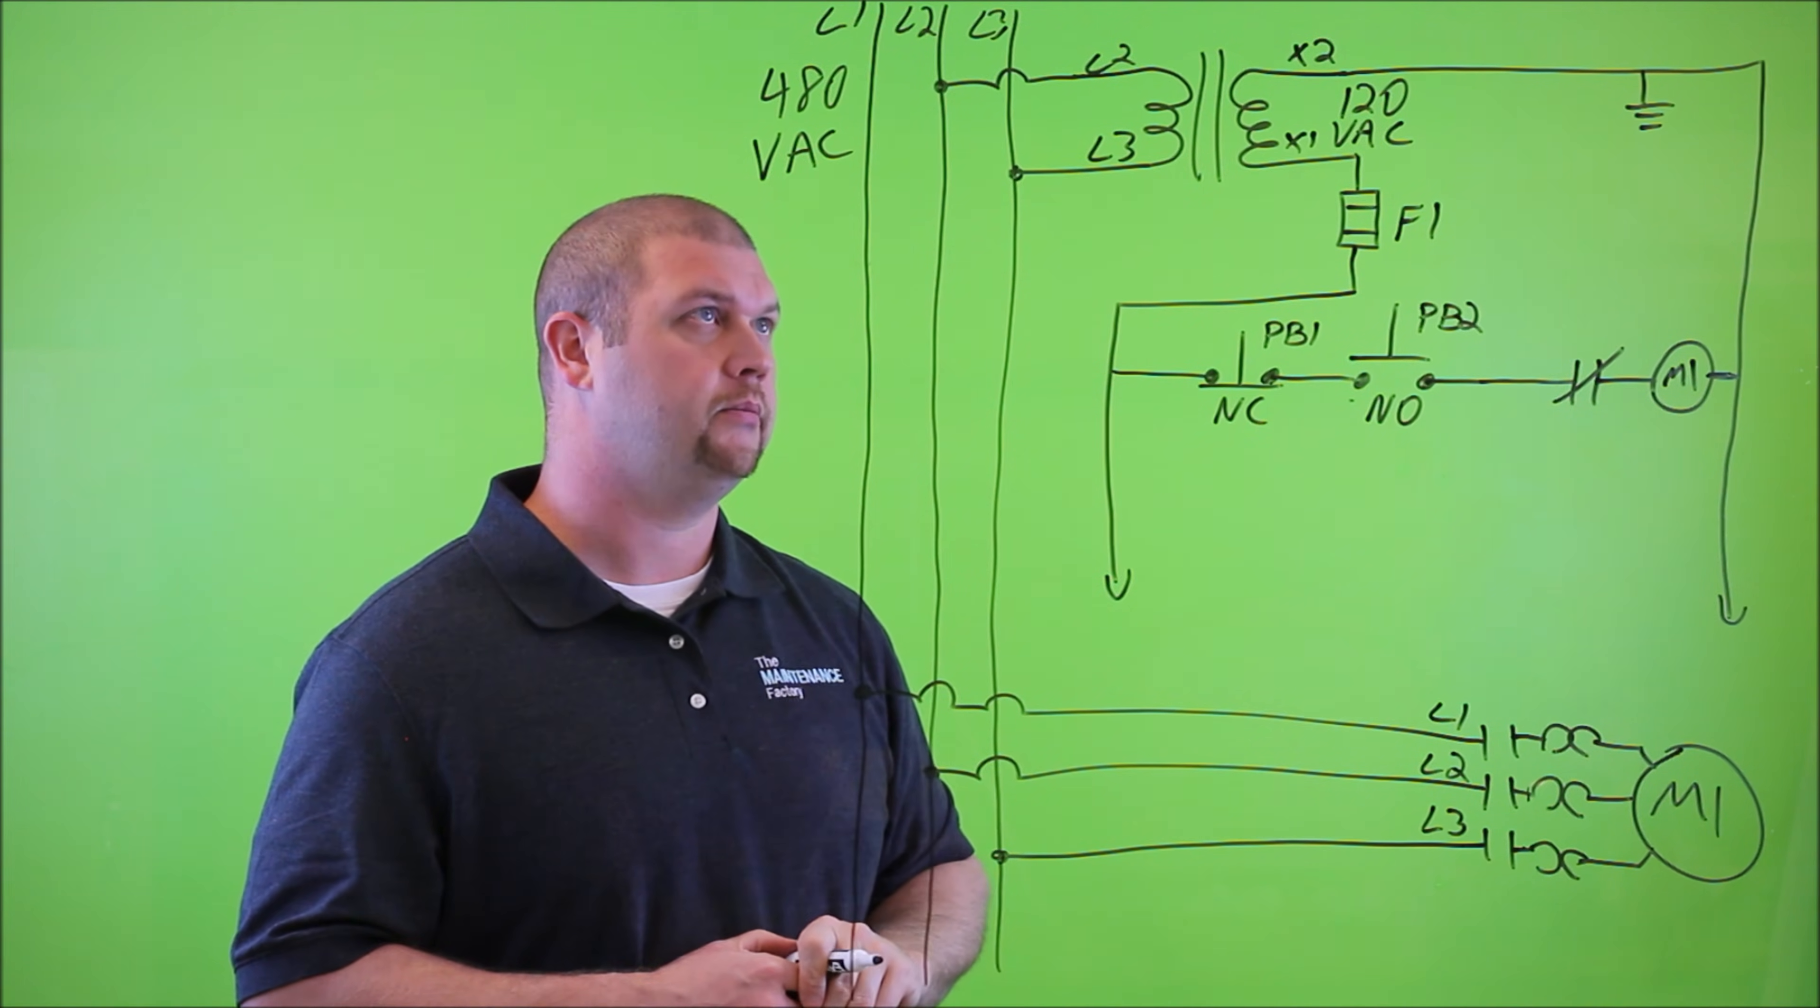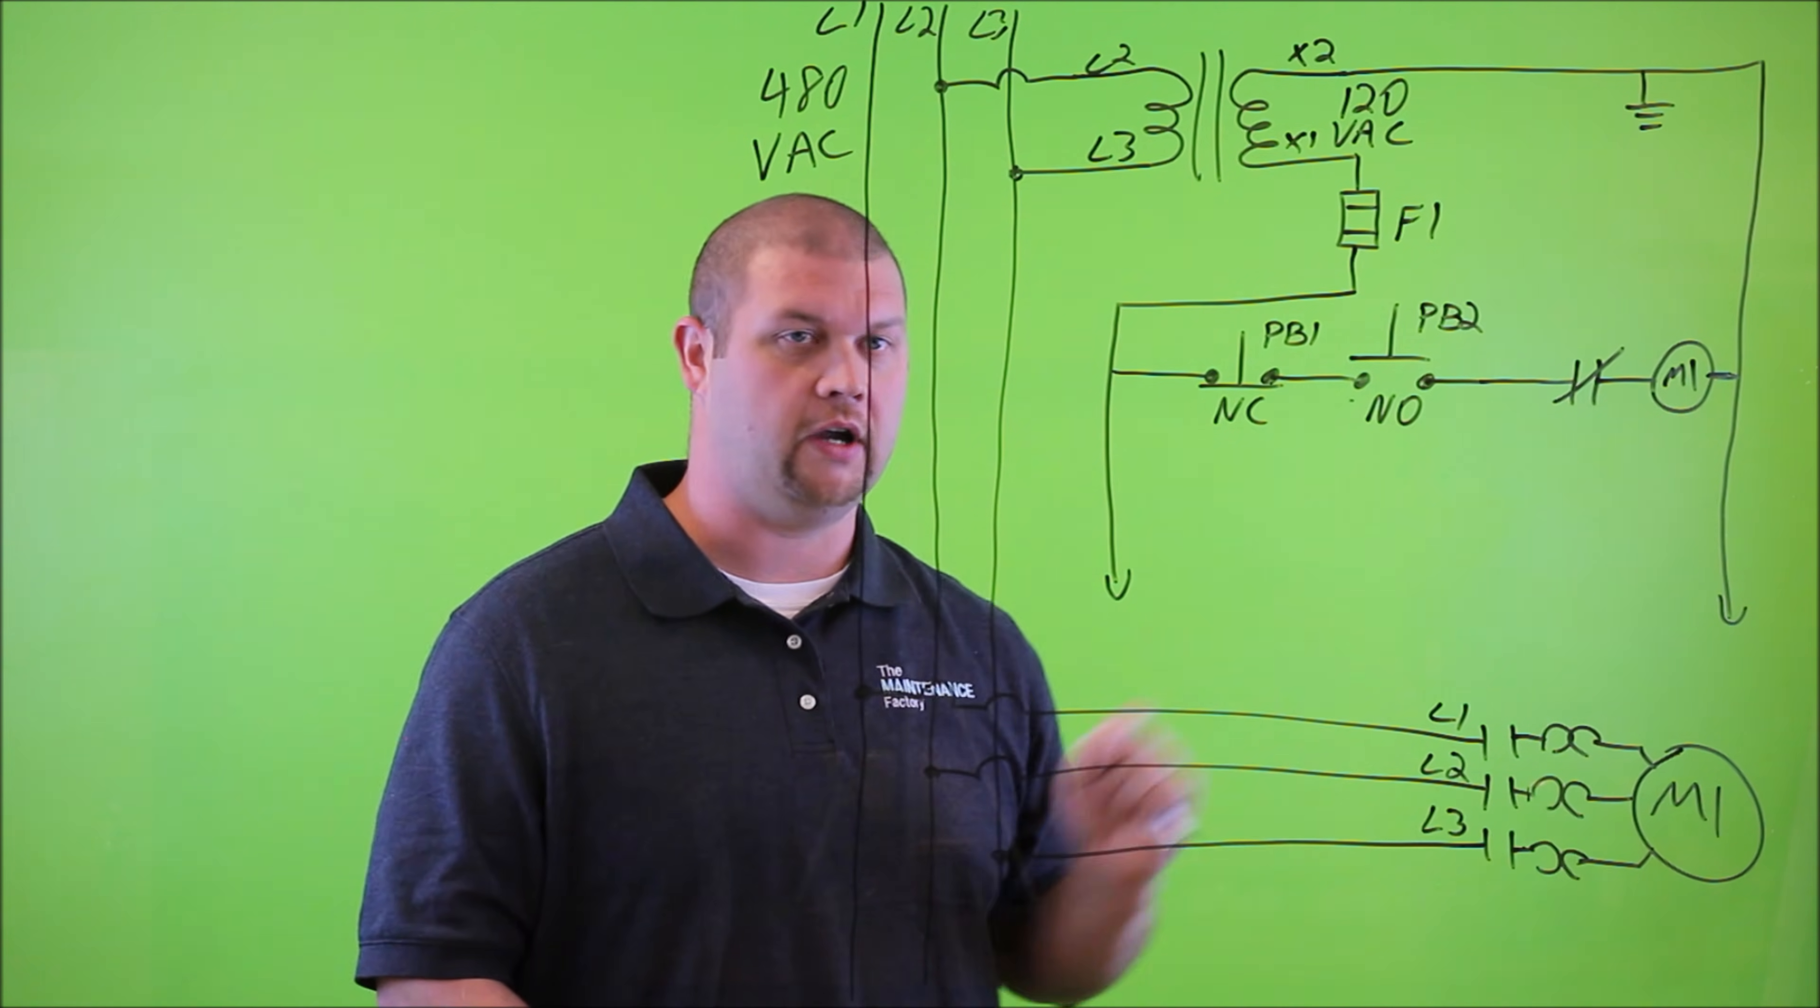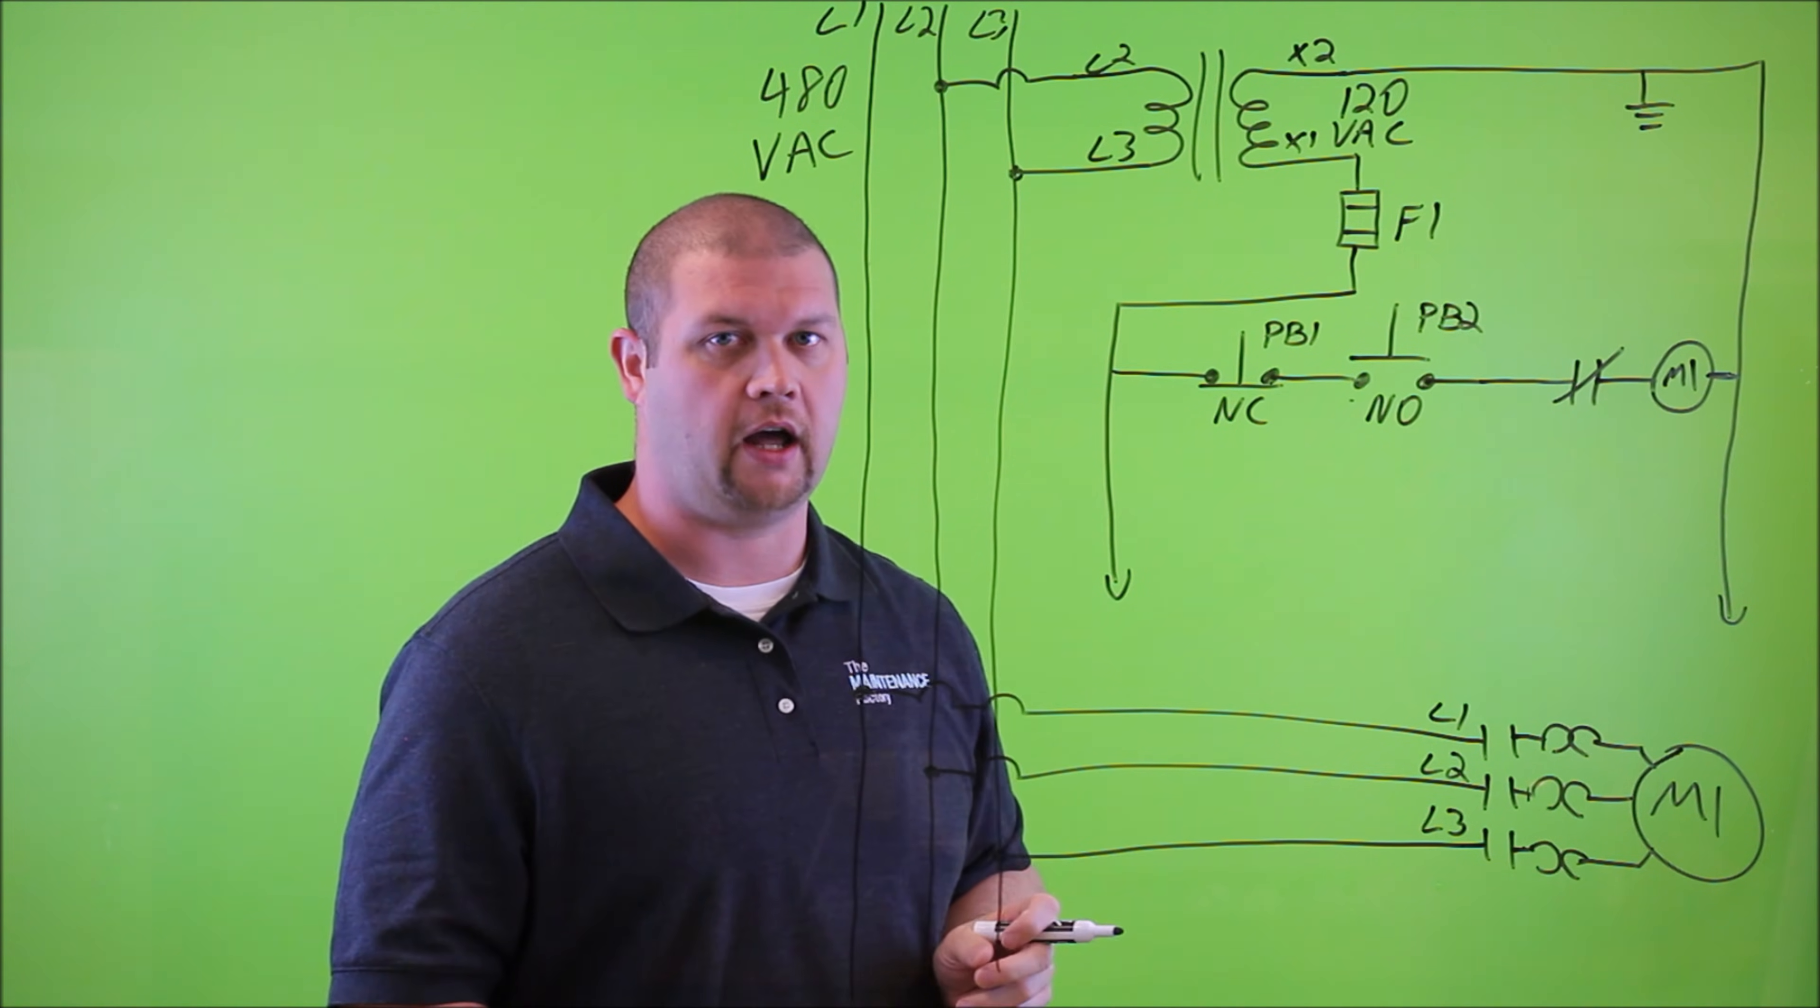Now, before we go any further, because there's one very important piece of information left out, I want to review what we have and walk through the steps on how this circuit would work in its current state. So, once again, we have our three phases of power coming in, 480 volts AC. It's three phases, and we know that because there's three lines. Each line is connected to the line side of the contactor, labeled L1, L2, and L3. The contactor has another device attached to it called an overload protection device. And then we have the motor.